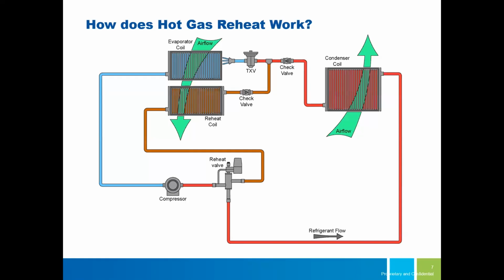I'm more the real world engineer, like any typical person in the room, going by what I've seen. Obviously, there's another version called modulating hot gas reheat, for bigger tonnage units, where you can control how much reheat you're actually getting, and that comes with bigger package units. But small package units, from what I've seen, 15 tons and below, you can't get modulating. I think it's all single stage, on/off reheat as we call it. And above 15 tons is where you have the option for modulating. Does that answer your question? Yes.